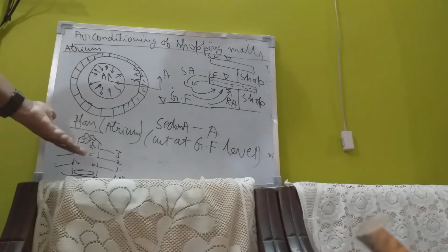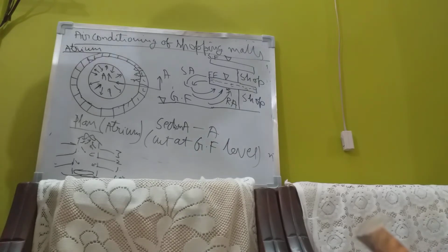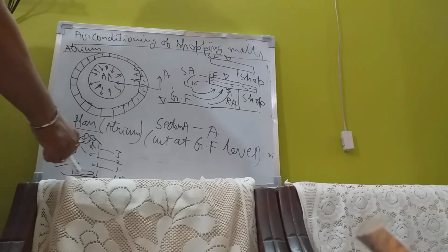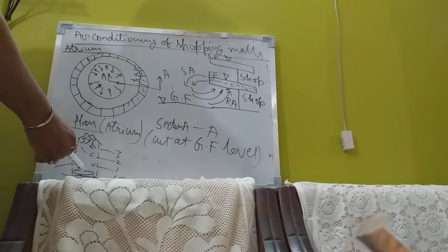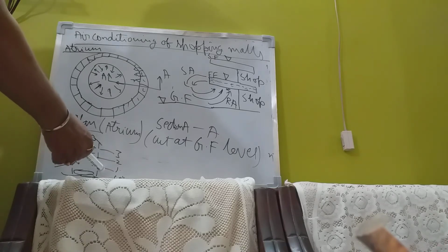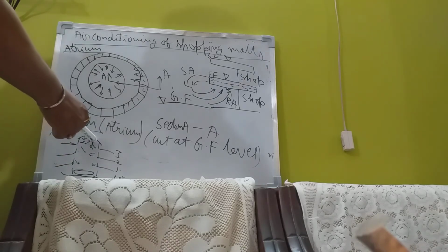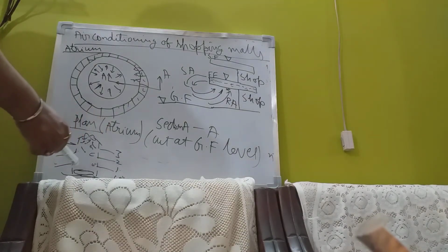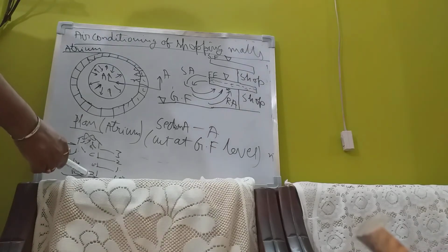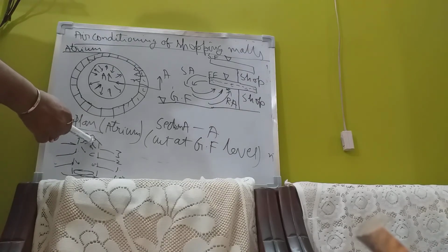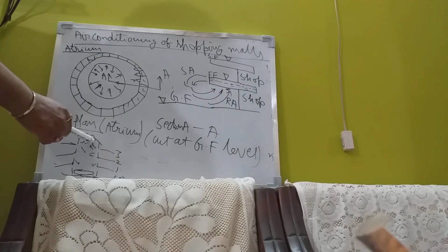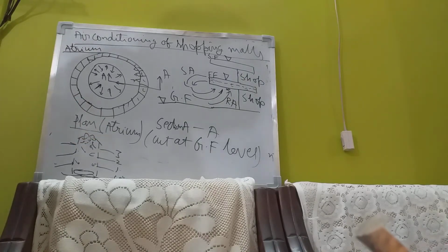The hot air has a tendency to rise. Say, for example, here you are supplying chilled air for cooling. This air picks up heat after coming here because of people and other things. After picking up heat it becomes hot. A part goes to the return air, another part comes up and forms a hot layer. The return air goes to the AC and gets cooled again and comes back. Again a part of it gets heated and goes up and forms a hot layer here. That hot layer goes out through the fan, and you are diverting it to the outside.